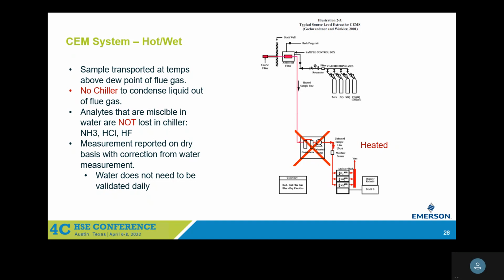So in order to do that, you have to do compensation by measuring water and calculating. So typically on a typical CEMS, we have on our NO laser also a water box. We measure NO and water together, which makes it very simple. And there are no water standards, so it's not something you validate every time. You have to validate the analytes that you're reporting. And this is working in the background, the same way that you're doing pressure and temperature compensation.